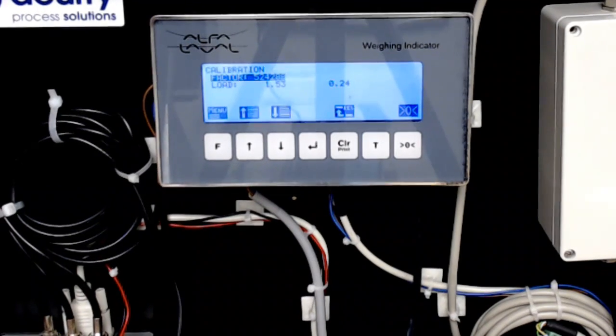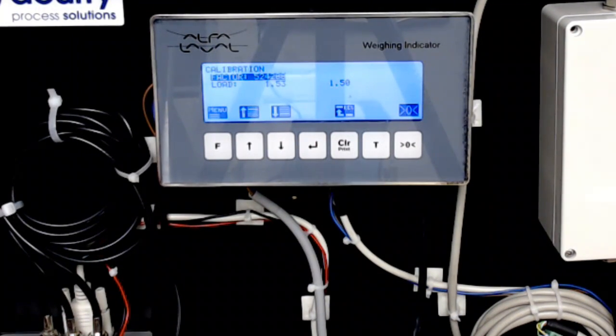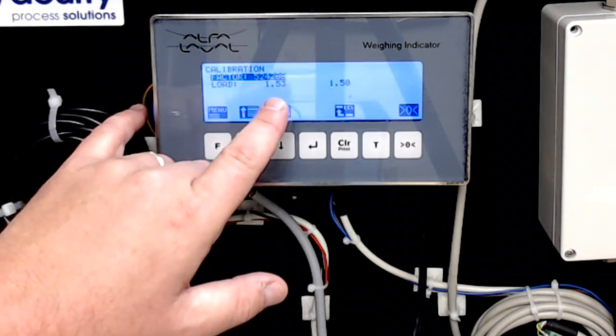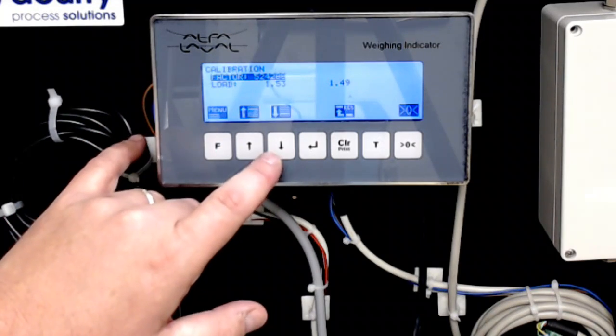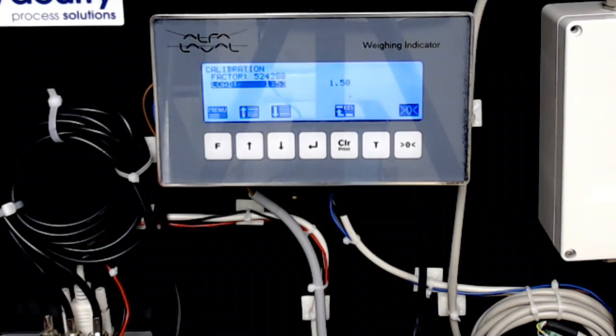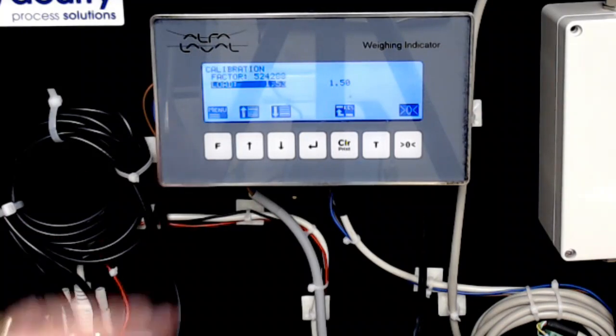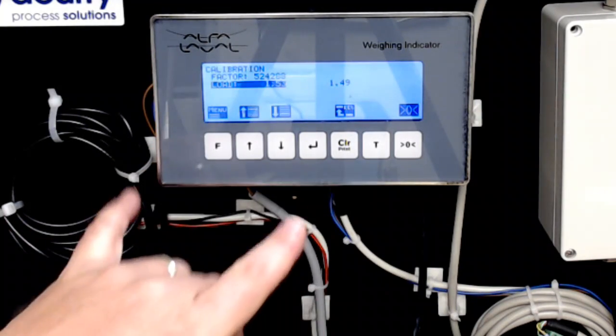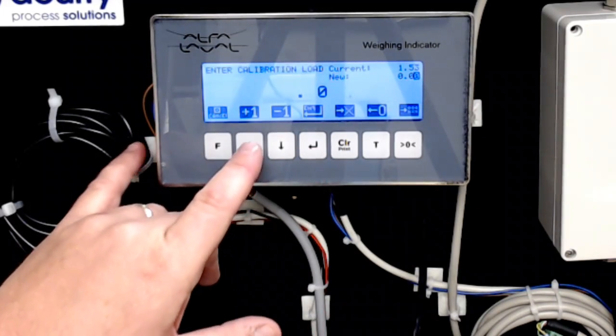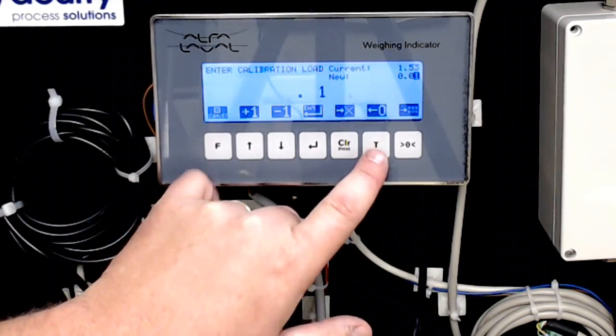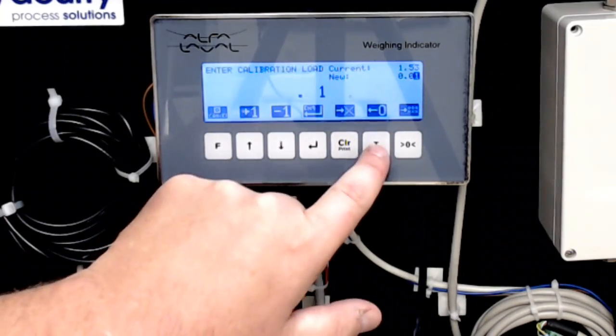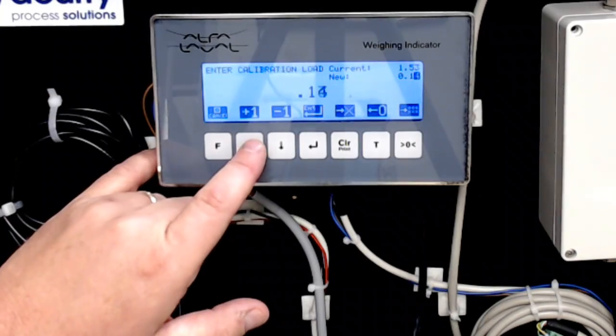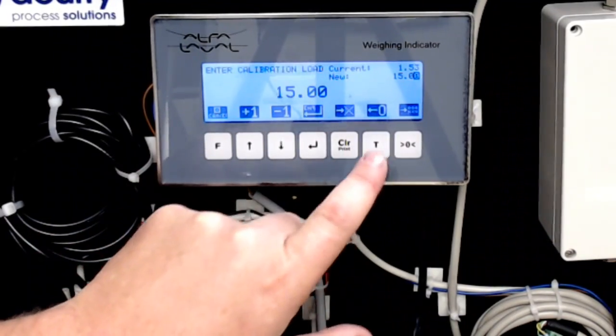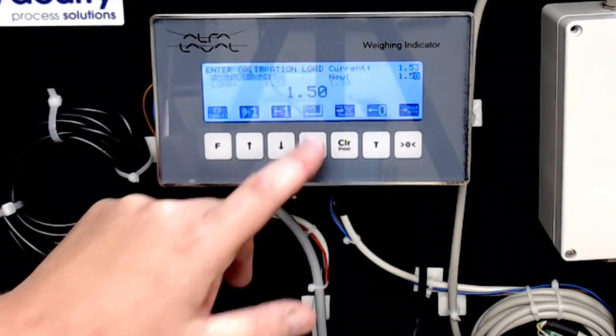I'm going to put a known weight on one of these cells. Okay, and that weight is going to read 1.50 approximately. Over on the right-hand side, you'll see here, I have the option, if I drop down into that screen, if I had a known weight that weighed 1.50 kilograms, and I'm bumping the camera here a little bit, so I'm sorry, that thing's got to stabilize, but if I went in here and said, okay, I know that the weight weighs 1.50 kilograms, that's what the system should be weighing. I'm going to enter that number here. We've gone through in a different session how to enter numbers, so I'm not going to waste time on that. But imagine we did that. Now we know this thing is 1.50.